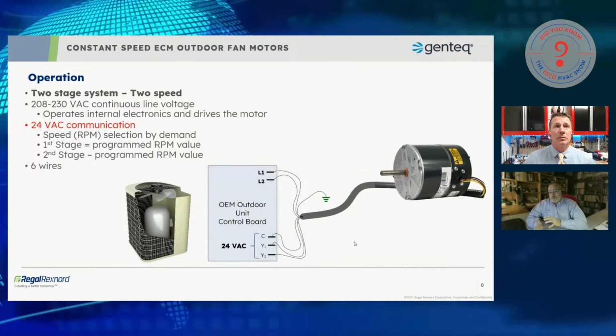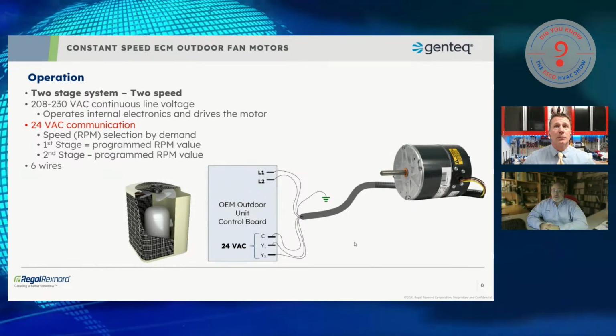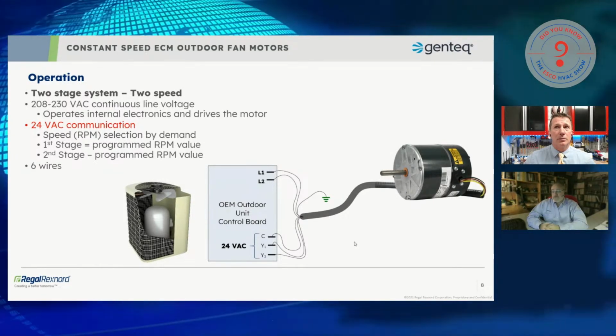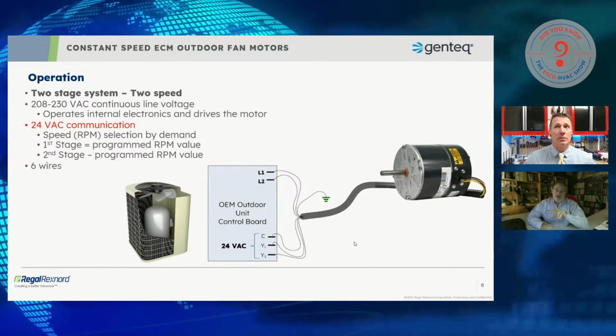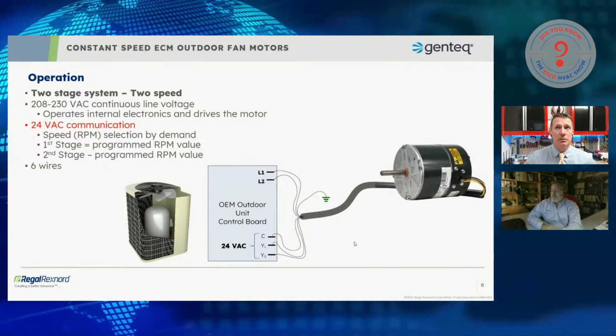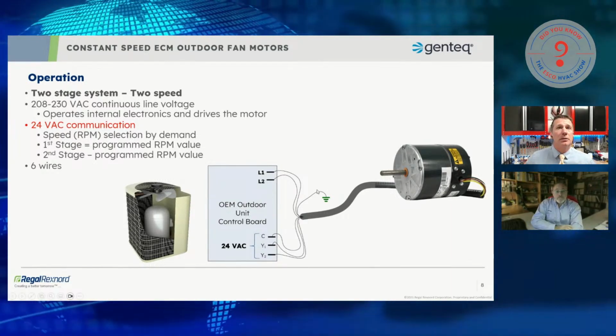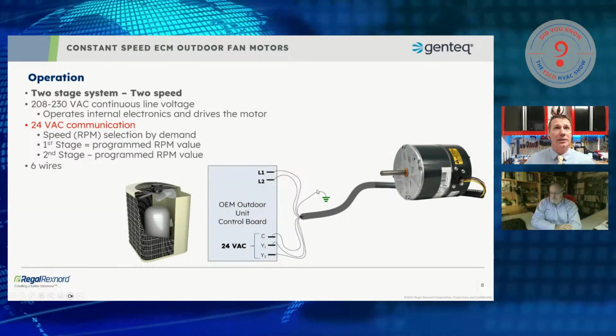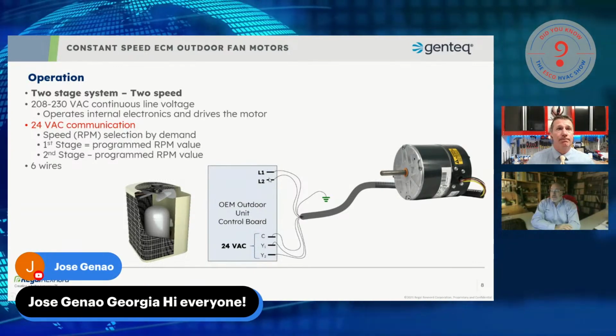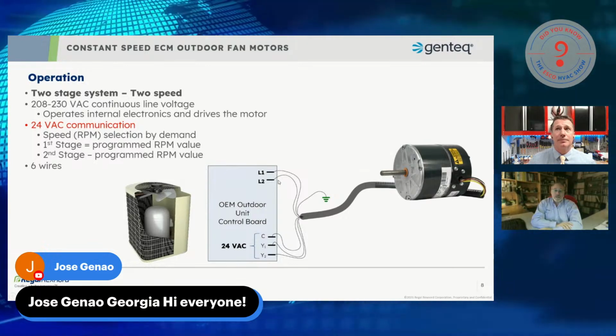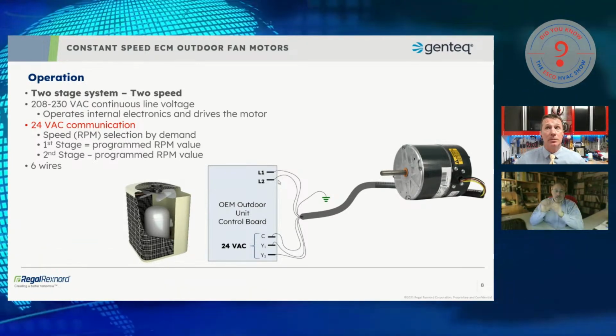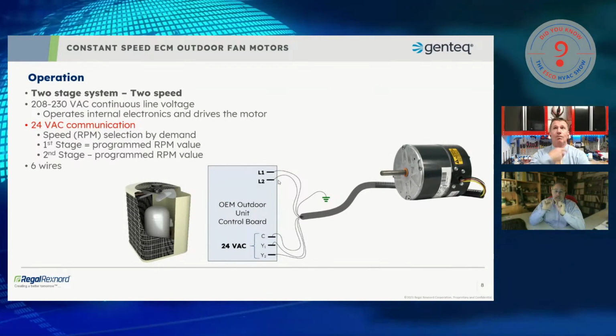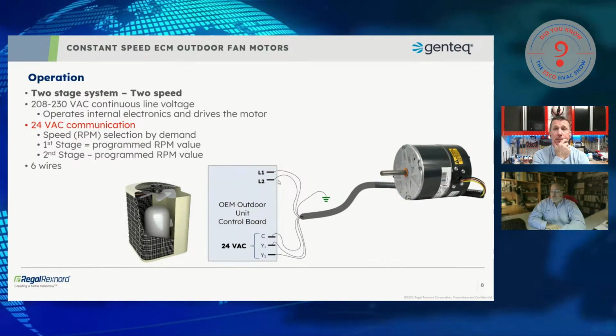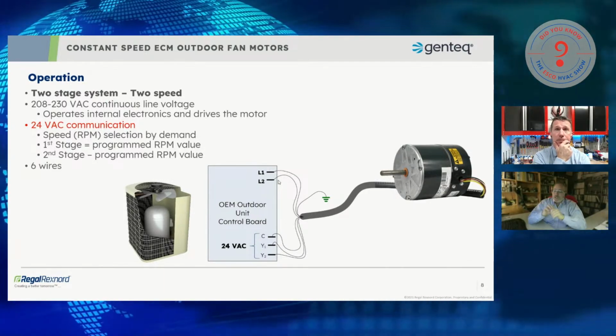Like all of the other motors that we've discussed so far, these motors are powered continuously with line voltage. So the 208, 230 volt power to the motor is continuously powered. L1, L2 is always hot on this one. Yes, sir. And that could be back to the circuit board. That could be directly to the load side of the contactor, where as soon as the contactor pulls in, I've got line voltage directly to the motor. So that voltage is continuous.